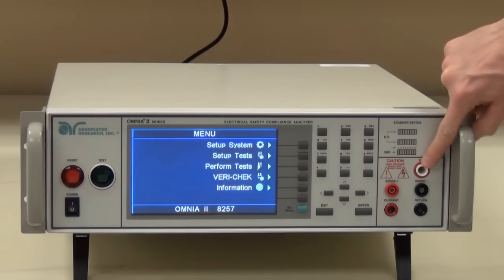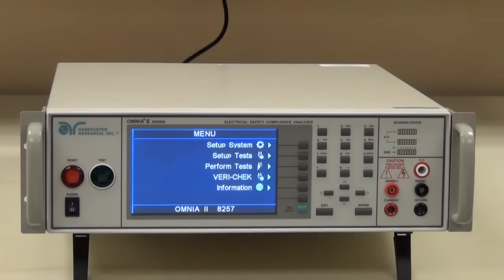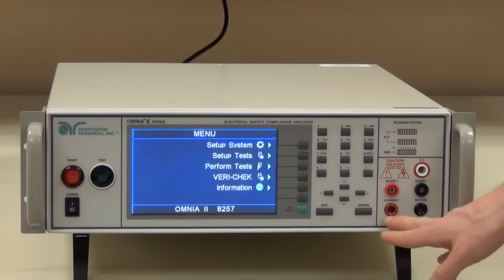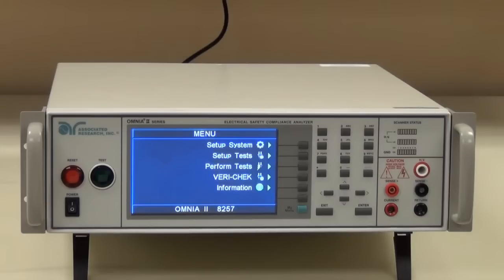The high voltage terminal will output high voltage to the device under test when you're running a high pot or insulation resistance test. The current port will actually output high current as well as low DC current for the ground bond and DC continuity test.